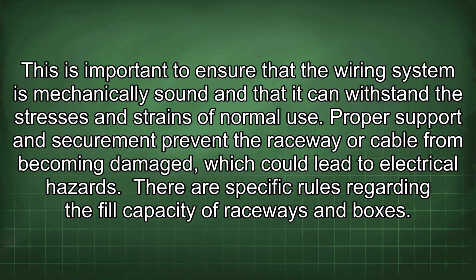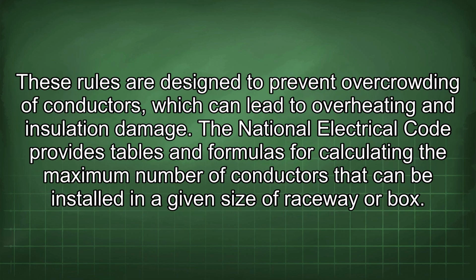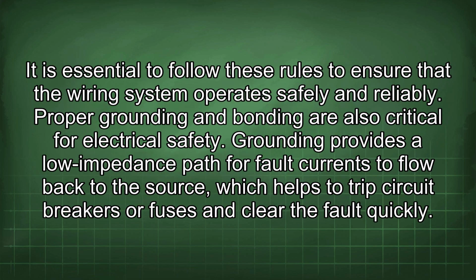There are specific rules regarding the fill capacity of raceways and boxes. These rules are designed to prevent overcrowding of conductors, which can lead to overheating and insulation damage. The National Electrical Code provides tables and formulas for calculating the maximum number of conductors that can be installed in a given size of raceway or box. It is essential to follow these rules to ensure that the wiring system operates safely and reliably.